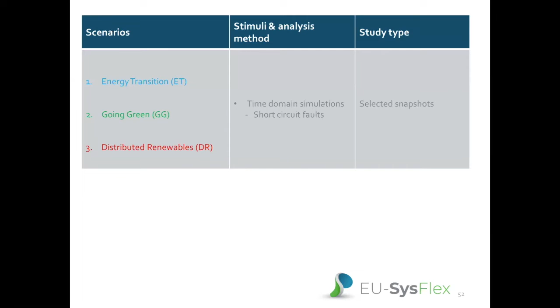Thank you, Hassan. For the purposes of dynamic voltage control analysis, we have applied the same approach as for the steady state voltage control. We have also analyzed three capacity scenarios. Low voltage fault ride through curves have been analyzed based on the time domain simulations performed alongside the transient rotor angle stability analysis. The analysis also has been carried out for the selected time snapshots. Voltage waveforms obtained from the RMS simulation have been compared with the low voltage fault ride through profiles required by the RfG, requirements for generators network code.